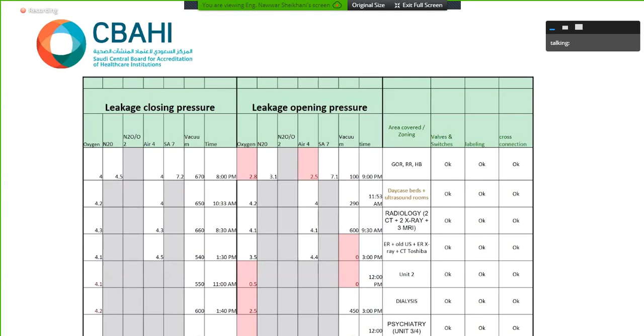This is a sample in an area valve service unit where we are getting the readings, where it should be at least 4 bar in medical air. We found it 2.5. It does mean we have a leak, for instance. This is valid for vacuum and for the nitrogen side and medical air as well.